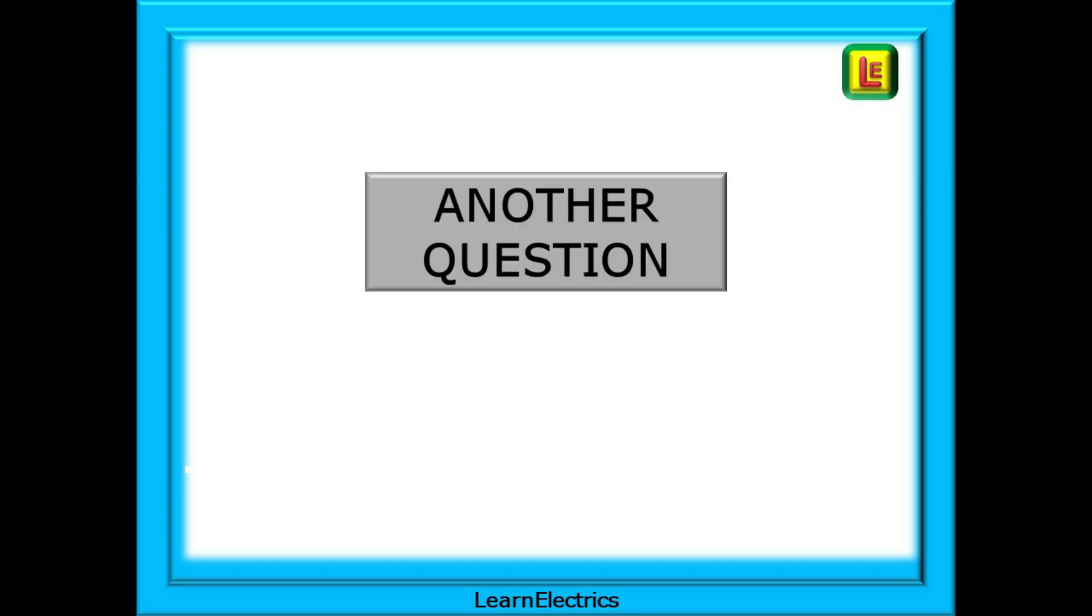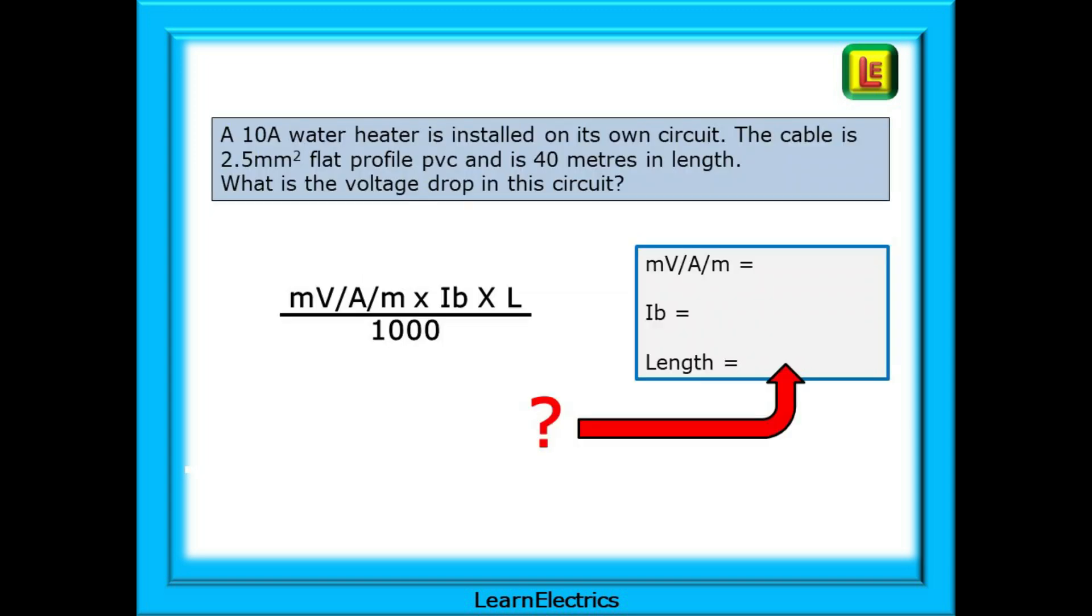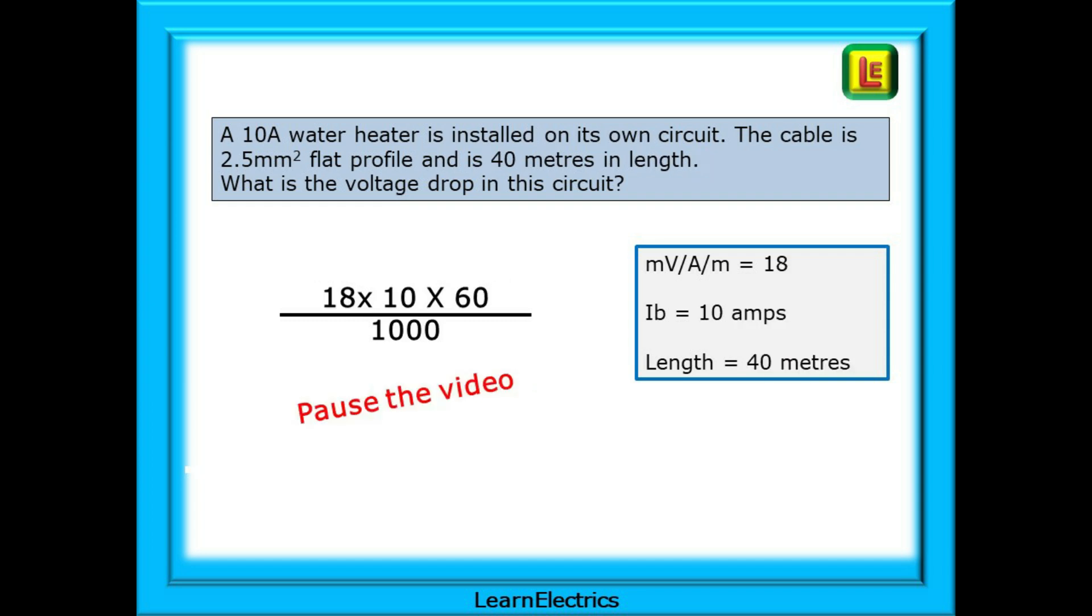Let's try another question on voltage drop. A 10 amp water heater is installed on its own circuit. The cable is 2.5 square millimetre flat profile and is 40 metres in length. What is the voltage drop in this circuit? Here we have the data from the question entered into the little box. Pause the video and have a go at answering the question. You should have an answer of 7.2 volts for the actual voltage drop for this circuit.